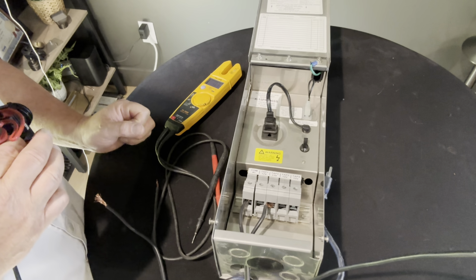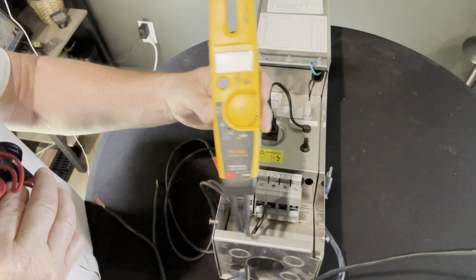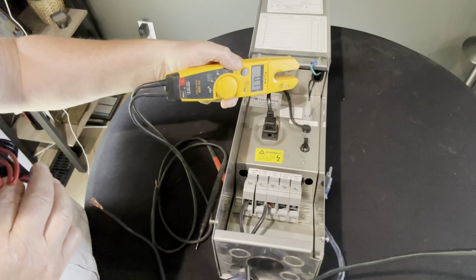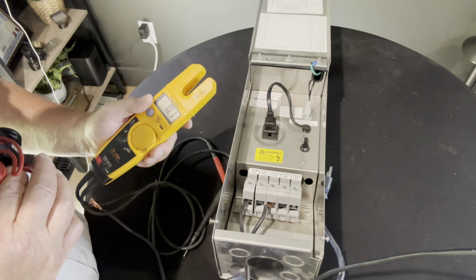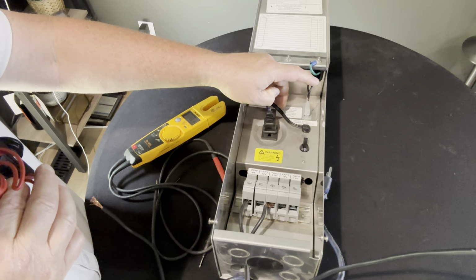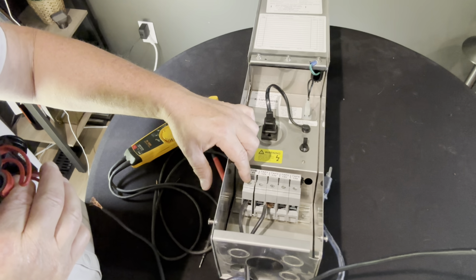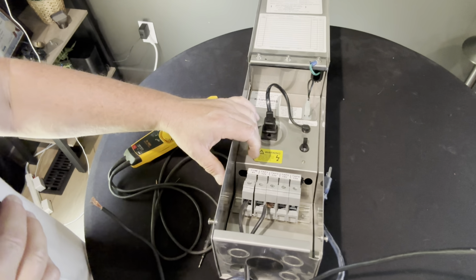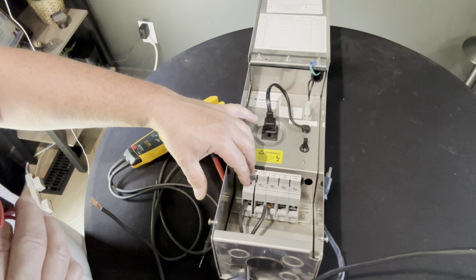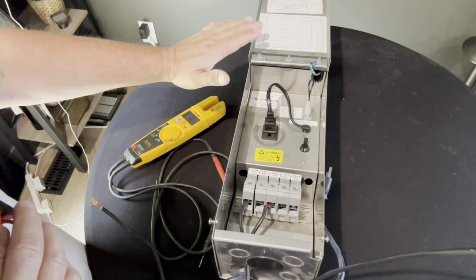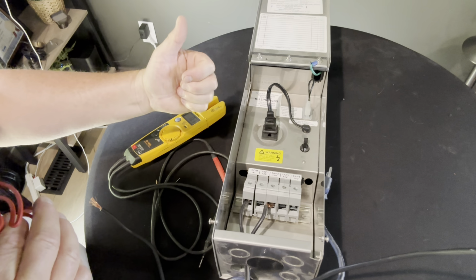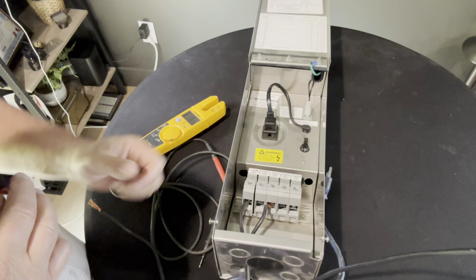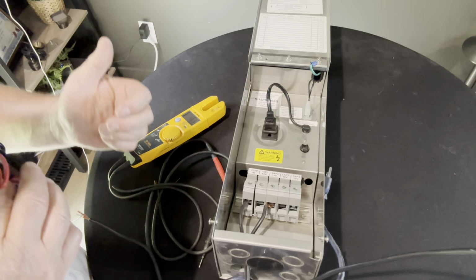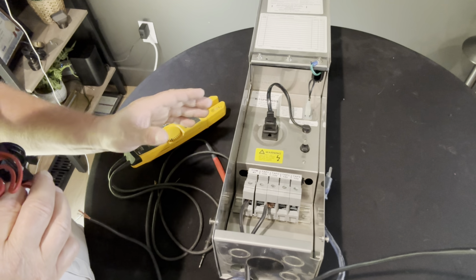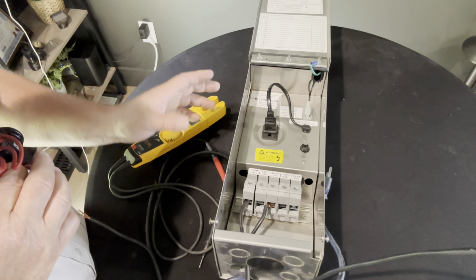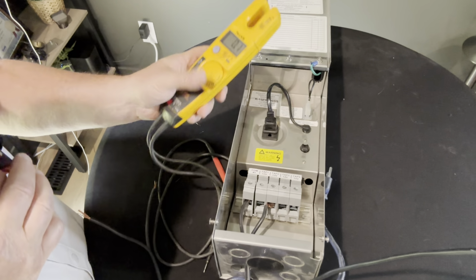Guys, if you have any questions on this, please ask me. It is so critical that you have a voltage meter and you know how to use it, and you do your testing when you hook up a system. Also, knowing your numbers, knowing that you can't exceed 2.5 amps here, knowing that you can't exceed 24 amps on the secondary side, knowing that you can't exceed 240 watts on this 300 watt transformer, or we have to use 80% of the capacity of the transformer, that helps you troubleshoot. So when you go out and you're having problems and you don't have lights on, or your secondary fuse won't stay on, it just shuts off, you know what to be testing for. Now that's all going to be listed in your ebook for you, so you have all that information, but it is important that you learn those numbers and you learn how to use a voltage meter.